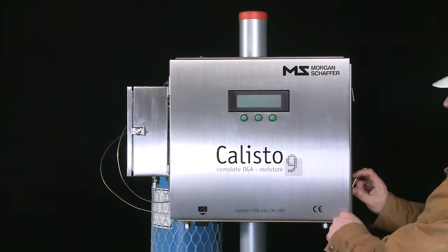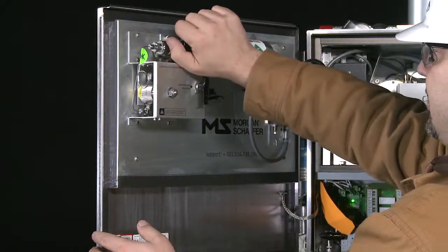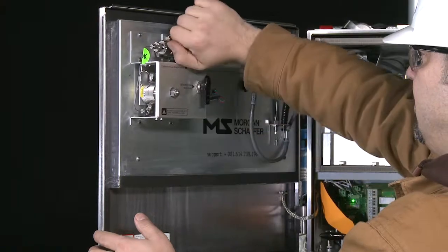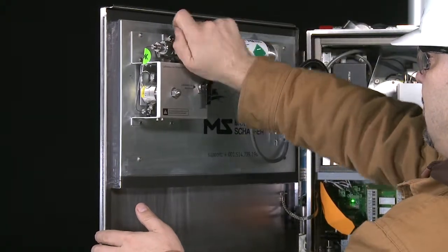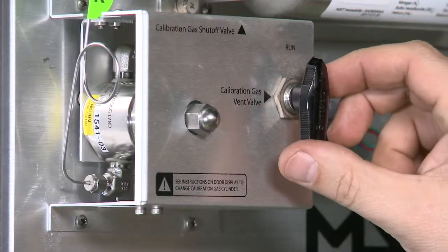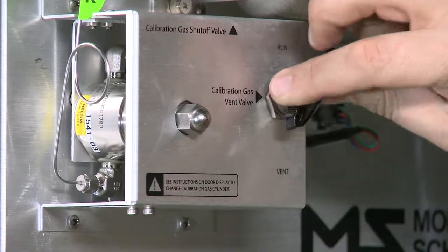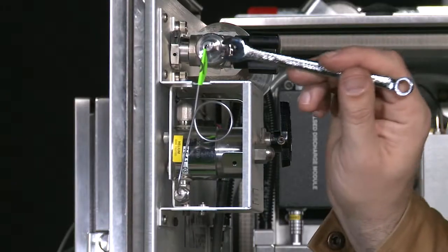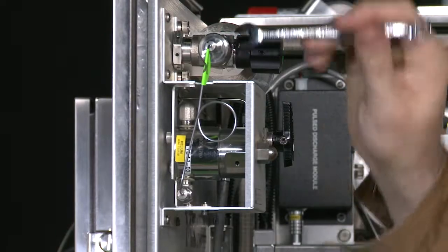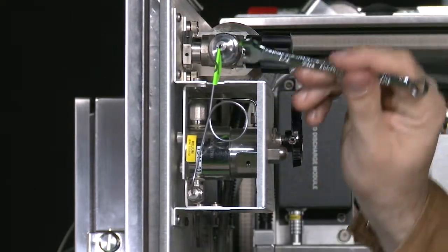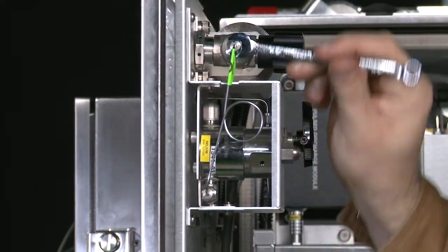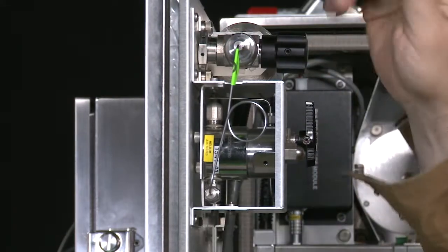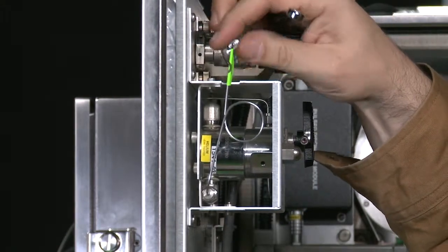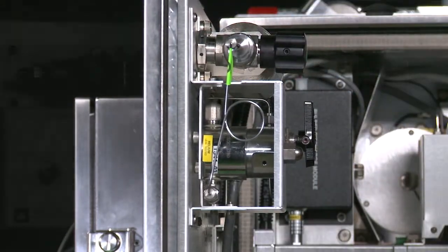Open the Calisto door. Close the shutoff valve on the calibration gas cylinder until a moderate resistance is encountered. Turn the module control valve knob to the vent position. Disconnect the fitting from the gas cylinder using a 5/16" crescent wrench on the fitting body to turn the nut counterclockwise. Remove the tube from the cylinder fitting by pulling on the nut.